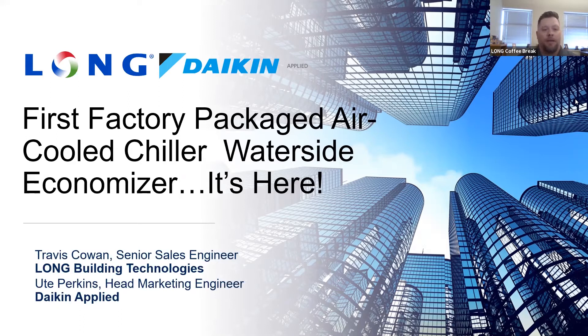Today we will be introducing the first factory packaged waterside economizer installed 100% at the factory on a fully configurable air-cooled chiller. Why is this important to us in Colorado? On water-dominant systems such as four-pipe fan coil units, it's a constant challenge to meet ASHRAE 90.1. We currently approach this with water-cooled chillers and towers or fluid coolers in conjunction with air-cooled chillers. Now we can utilize a waterside economizer on a high-efficiency air-cooled screw chiller with IPLVs well over 20-plus IER.